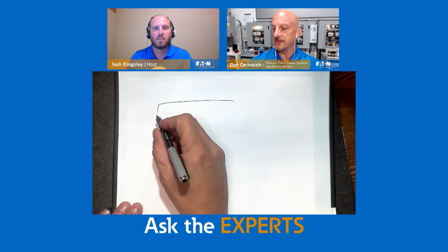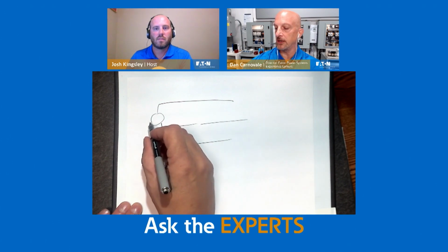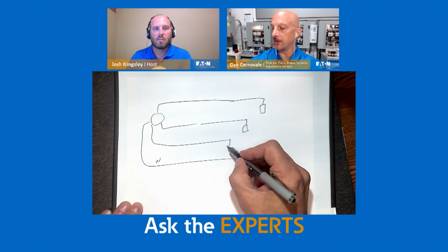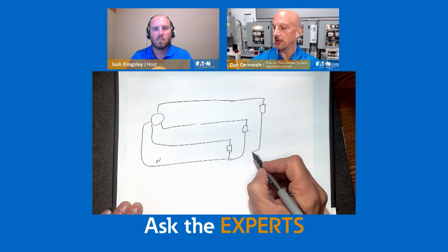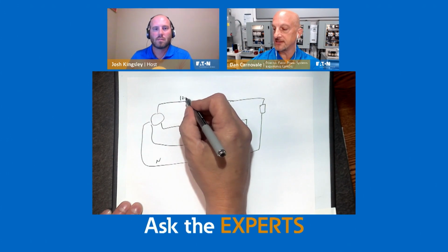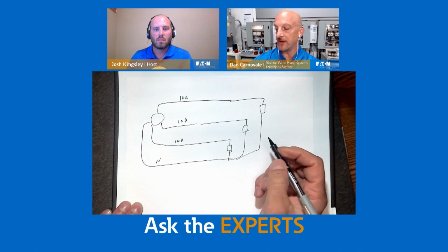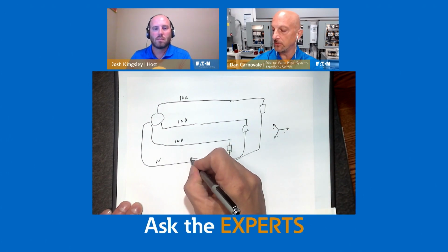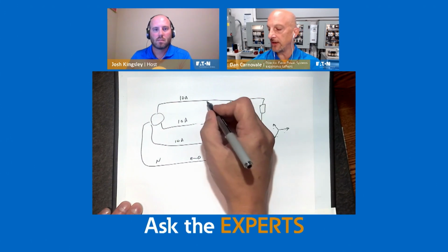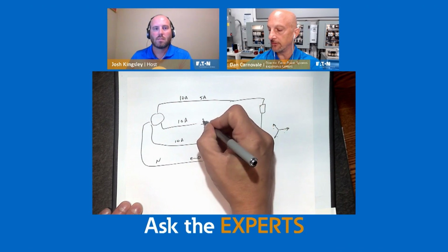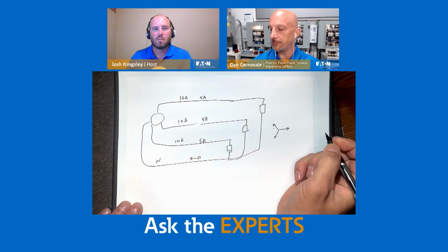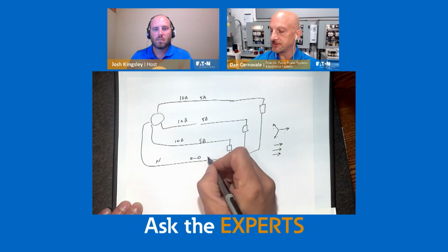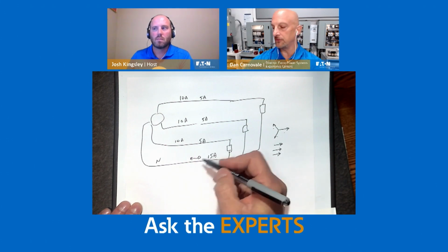So if we look at a three-phase system, with three phases going out and a neutral, what you're referencing is, if I have loads on each phase connected to neutral, you were talking about zero sequence a little bit. Let's say phase A has 10 amps, phase B 10 amps, phase C 10 amps. If that's 60 Hertz current, because it's all displaced by 120 degrees, 10 amps plus 10 amps plus 10 amps in the neutral, we get zero. But what's interesting is you mentioned zero sequence. If I have, let's say, 5 amps or 10 amps or whatever of third harmonic or zero sequence current, that current is actually additive on the neutral. So when it gets back to this point, it's 1, 2, 3, and it adds up to be 15 amps in this case. That's why people historically have doubled neutrals.